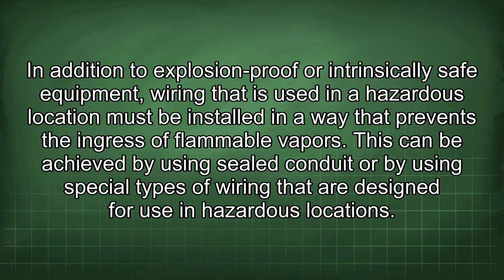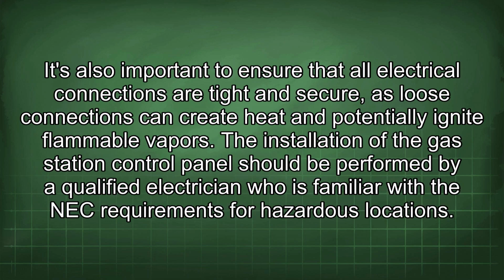This can be achieved by using sealed conduit or by using special types of wiring that are designed for use in hazardous locations. It's also important to ensure that all electrical connections are tight and secure, as loose connections can create heat and potentially ignite flammable vapors. The installation of the gas station control panel should be performed by a qualified electrician who is familiar with the NEC requirements for hazardous locations.